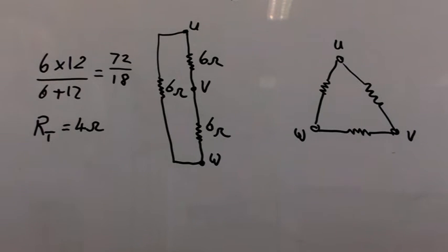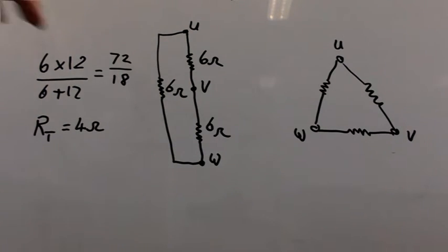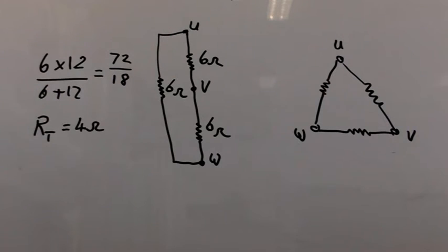So if I put my meter, multimeter across U and V then I would read 4 ohms. If I put my meter across V and W I would read 4 ohms and if I put my meter across U and W again I would read 4 ohms.